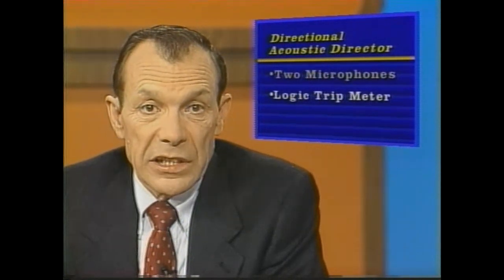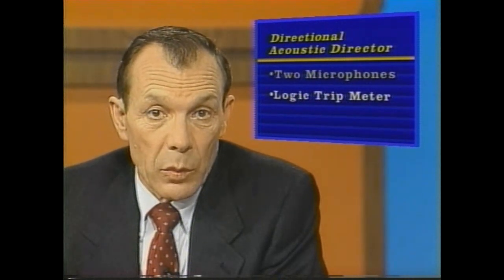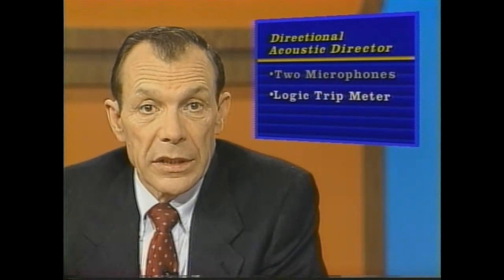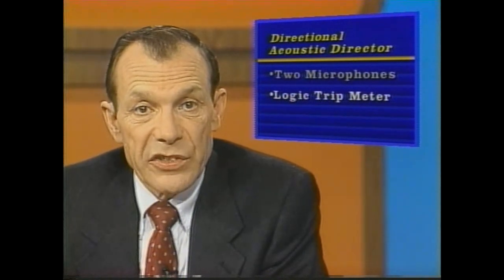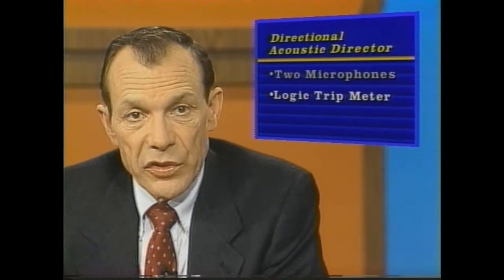A directional acoustic detector system has a zero center meter, like the one used on the earth gradient fault locator. It is called a logic trip meter. Each side of the meter is tied to one of the microphones. When the first microphone picks up the sound and locks out the second mic, the logic trip meter trips in the direction of the microphone that heard the sound first, indicating the direction of the fault. When you walk past the fault, the trailing microphone hears the sound first because it is now closer to the fault. It locks out the lead microphone and trips the logic trip in the reverse direction. This signals that you have passed the fault.